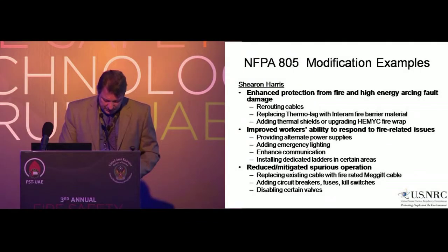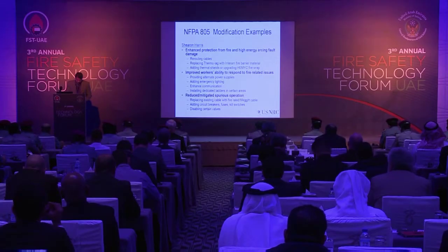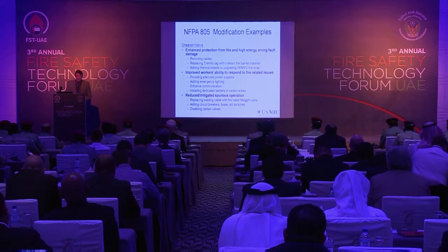During the NFPA 805 transition process, plants have taken a systematic look at their fire protection program and analyzed the program using both traditional fire modeling and risk-based techniques. This has led to an improved understanding of the fire protection program and the sensitivity of specific aspects of the program as they relate to the specific configuration and processes unique to the particular plant. In reviewing the license application, the NRC staff also developed a more complete understanding of the aspects of the program that have had a significant impact on fire risk. Because of this improved understanding by both the utility and the NRC, enhancements could be proposed and implemented by the licensee and approved by the NRC such that the overall fire risk was reduced. Typically, these enhancements go beyond what is required in the previous licensing basis.